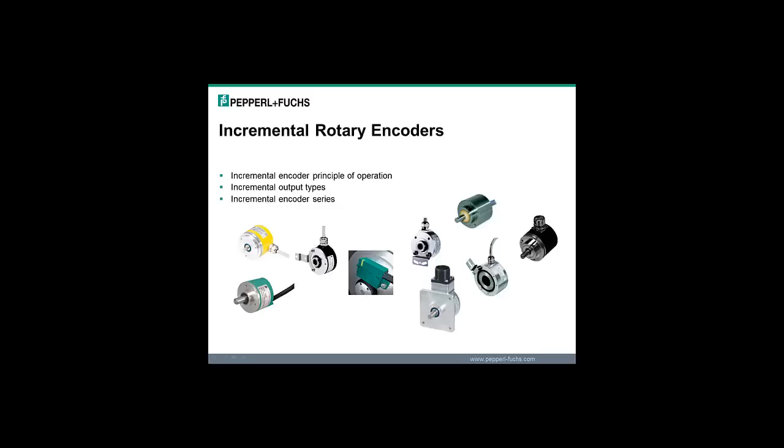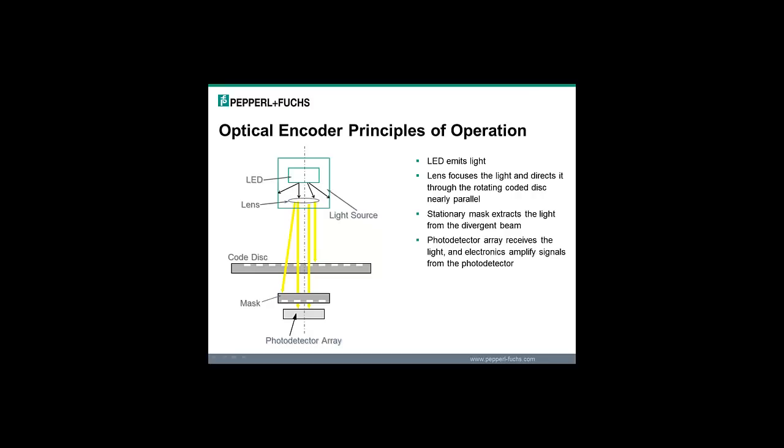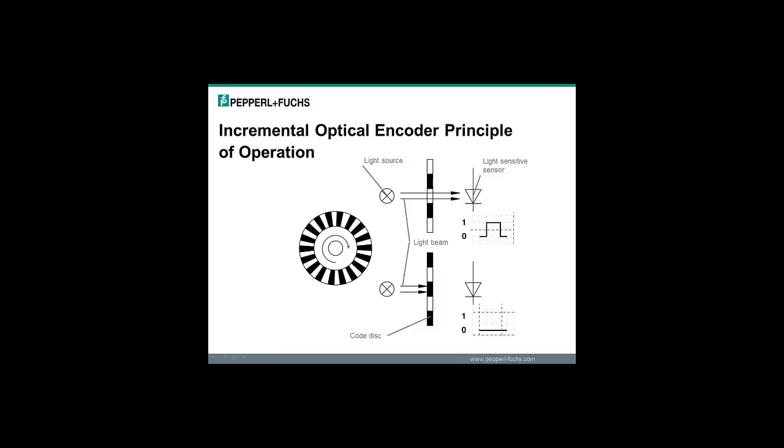The next section is for the principle of operation, output types, and different series available for incremental rotary encoders. The optical rotary encoder has an LED with a photo receiver array that will receive the light and then be amplified and conditioned. There is a code disk that will determine the resolution and it has slots or clear spots that allow light to go through and opaque or covered spots that will prevent light from going through. This slide shows the type of signal generated when the light goes through the code disk or if the light is blocked. So if you have 360 clear and blocked segments on the code disk you will get 360 pulses per turn. The number of pulses per turn will help determine the resolution.